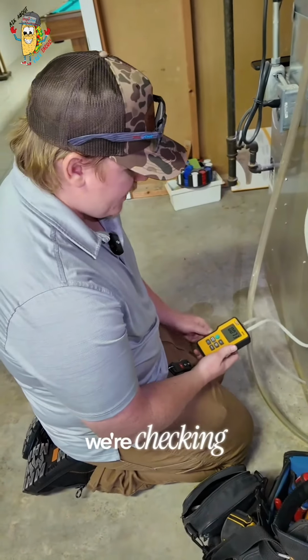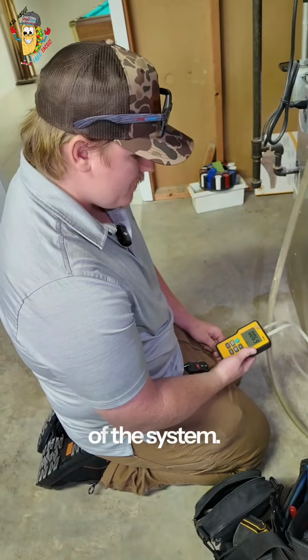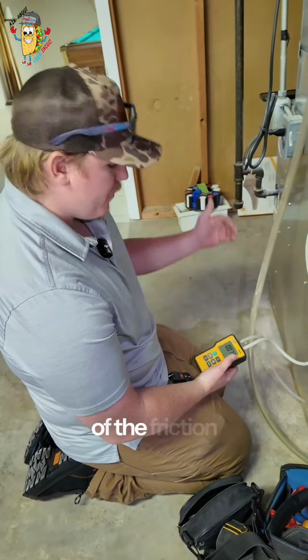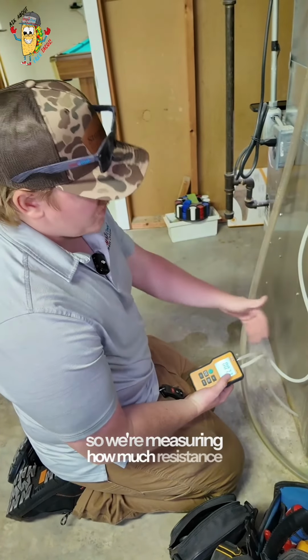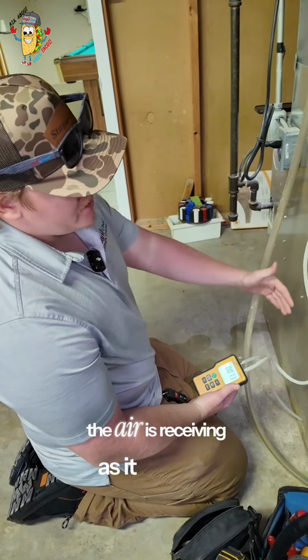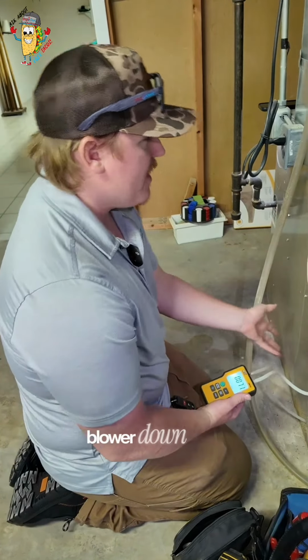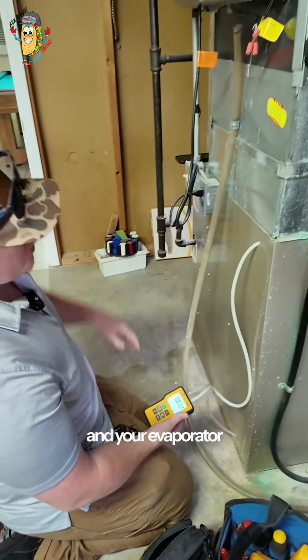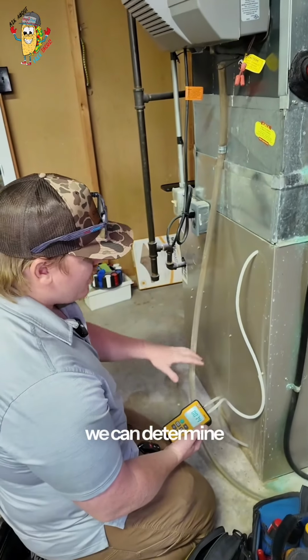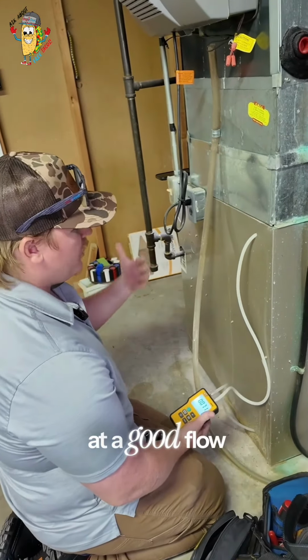Right now, we're checking the static pressure of the system. Static pressure is basically a measurement of the friction of air. So we're measuring how much resistance the air is receiving as it travels through the furnace. So you have your blower down here, your heat exchanger, and your evaporator coil.